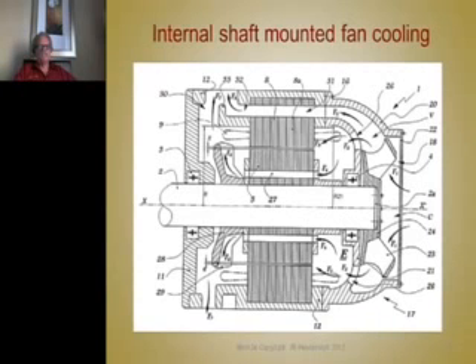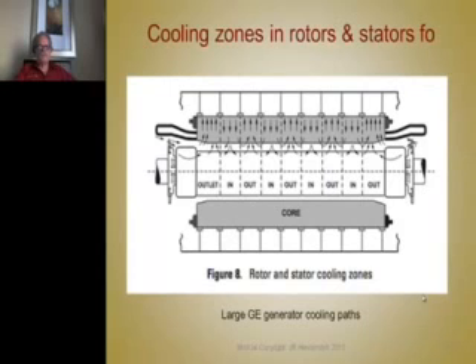This is a small motor that has a kind of a clever centrifugal fan mounted here. See, where's the inlet? I'm looking. Oh, the inlet is through this screen here at the end, so it sends air through passageways in the stator yoke, like I described before, and out here it sends it through holes in the rotor, and it sends it through the air gap. And so some scheme like that you could certainly incorporate into a motor design. These are some cooling zone descriptions, rotor and stator cooling zones. This is from a very large General Electric power plant generator.